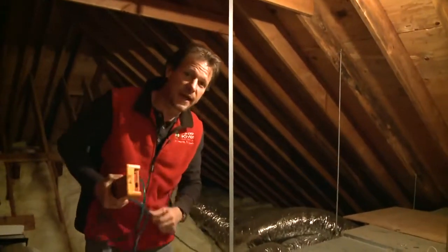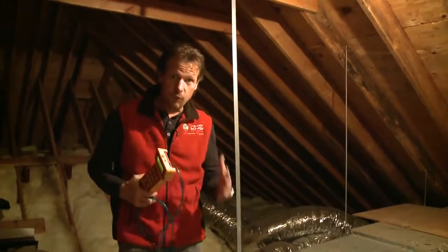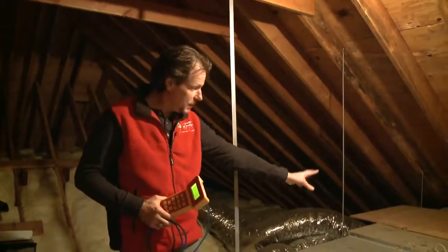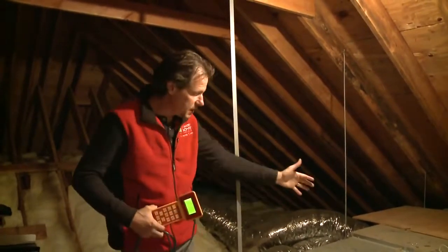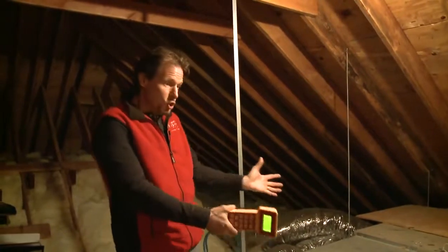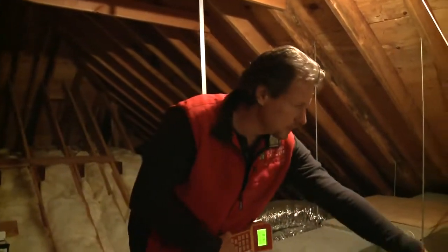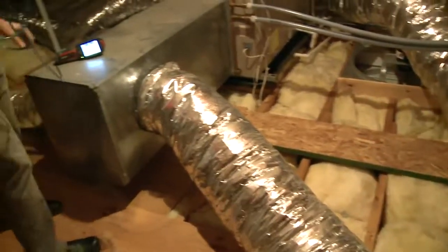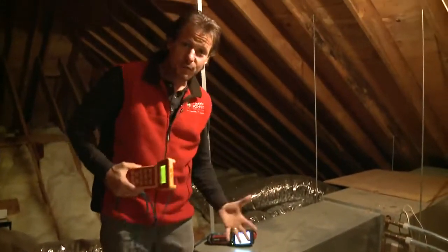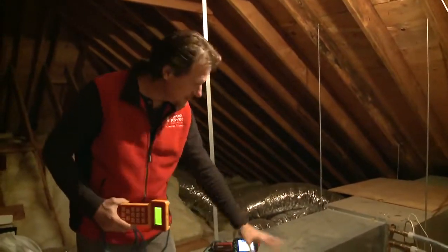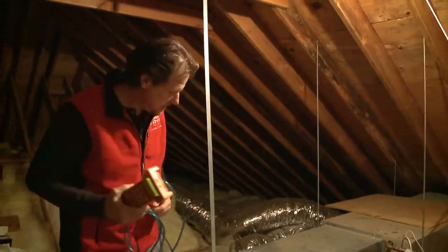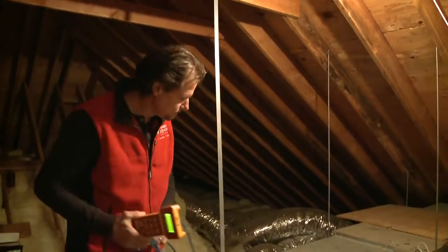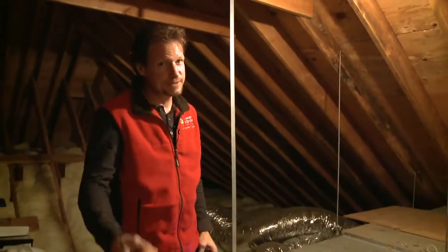So all this air, you are pumping, forcibly pumping, not just the stack effect, but you have a big 2000 CFM perhaps blower inside that cabinet, forcing air through these supply ducts and sucking air through the return duct. That's the return box right there, and the return duct goes in that end of the air handler, and all the supplies of the heated air comes out this end, and we are pumping air that we just paid to heat into this attic. So these are AA priority leaks, ducts in unconditioned spaces, particularly attics, which are hostile environments. Absolutely amazing, and we can fix this for you.